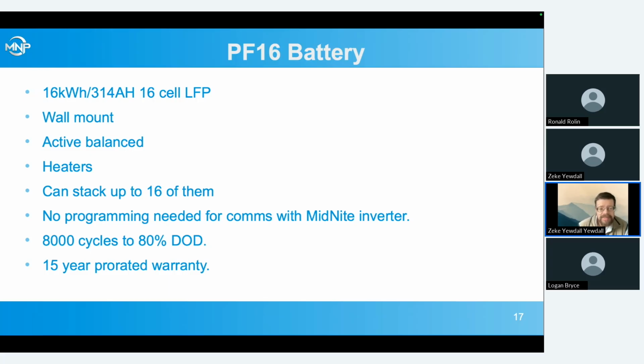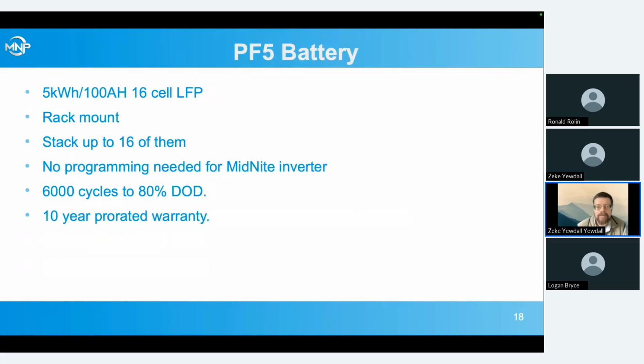And because these are actively balanced, we rate them for 8,000 cycles and give a 15-year prorated warranty. The PF5 rack mount batteries are passively balanced, which is like most of the batteries out there nowadays. And that's just not quite as good at balancing all the cells because it only operates when the batteries are just about full, kind of up there in the high 90s to 100%. Whereas the active balancing can do a lot better job at balancing because it's operating at more different points along the state of charge scale.